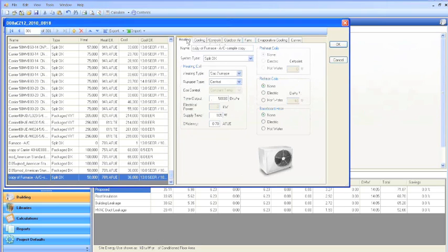For example, Energy Pro does not model whole house fans that are on a switch for the homeowner to activate, or work intermittently, or bathroom fans. Those are not entered into the model. The model has an assumed value for those. Only if there's a continuous fan draw would that be modeled in Energy Pro, and I'll get to that a little bit later.